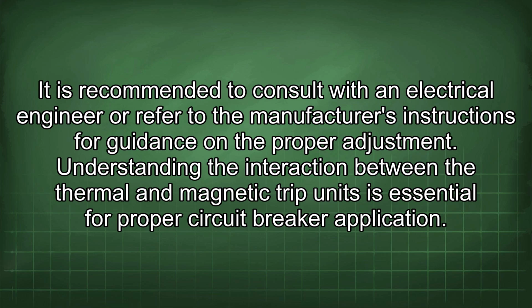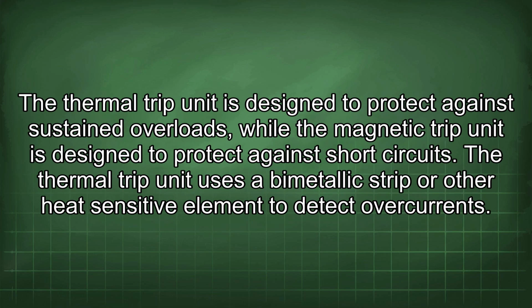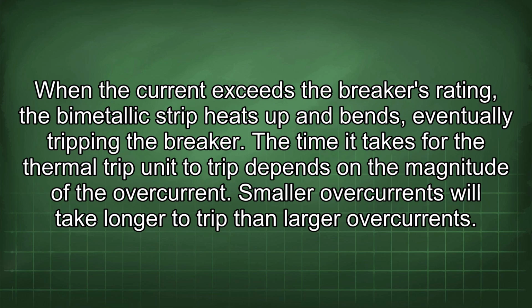Understanding the interaction between the thermal and magnetic trip units is essential for proper circuit breaker application. The thermal trip unit is designed to protect against sustained overloads, while the magnetic trip unit is designed to protect against short circuits. The thermal trip unit uses a bimetallic strip or other heat-sensitive element to detect overcurrents. When the current exceeds the breaker's rating, the bimetallic strip heats up and bends, eventually tripping the breaker. The time it takes for the thermal trip unit to trip depends on the magnitude of the overcurrent. Smaller overcurrents will take longer to trip than larger overcurrents.